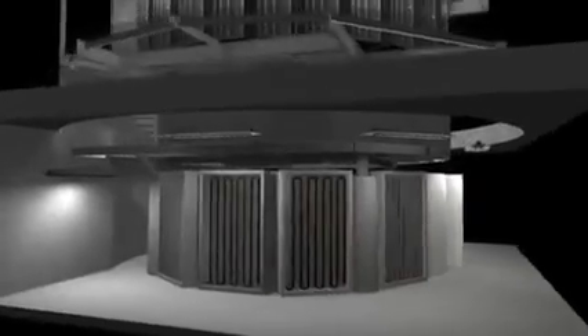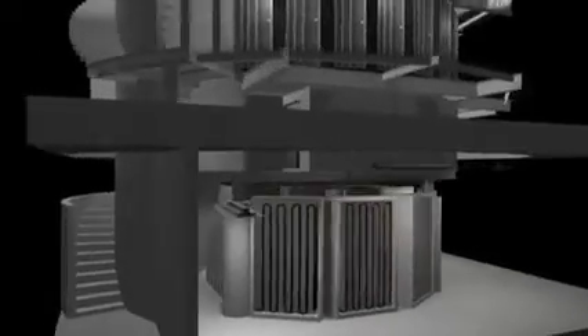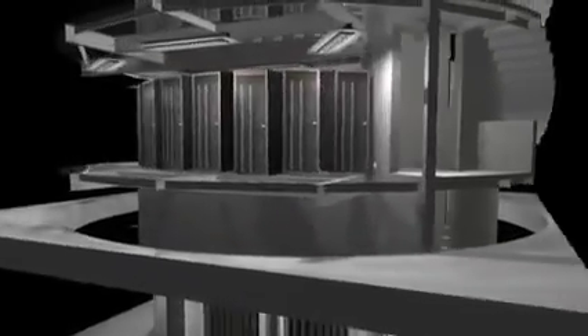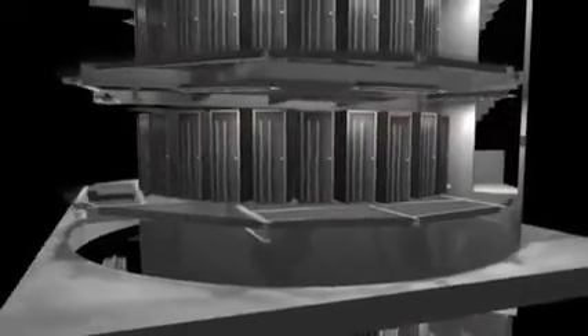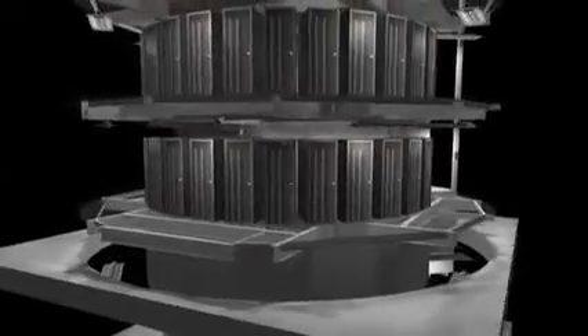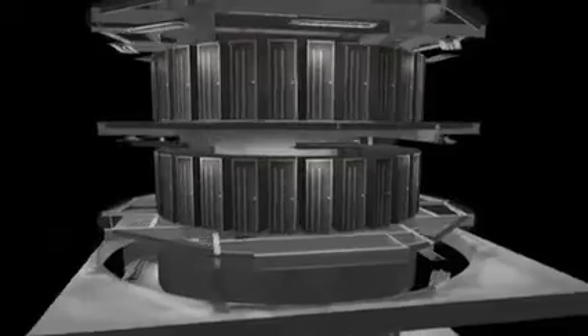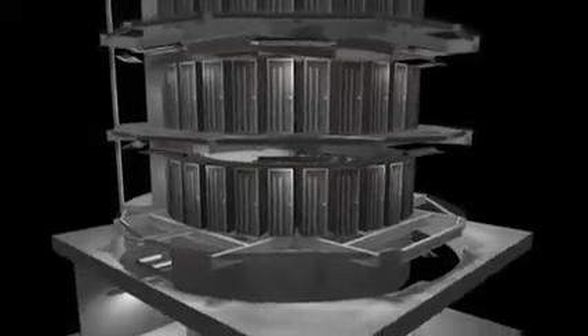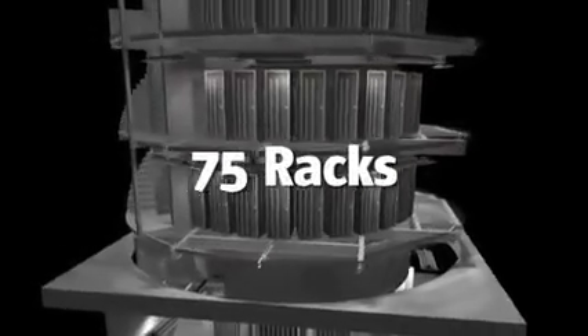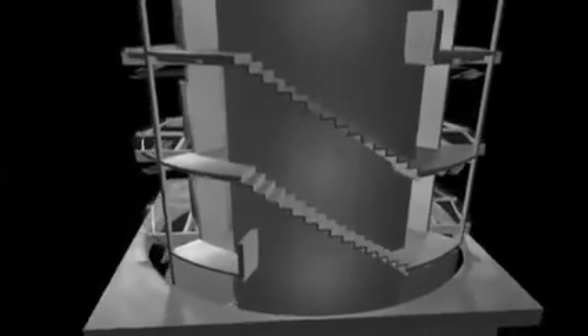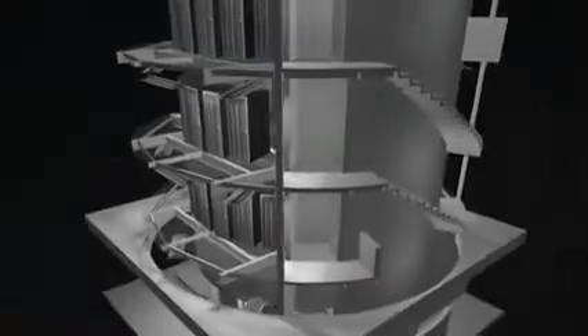The silo is built over 3 floors. You have a sub-basement with all the cooling infrastructure, and then 3 levels of compute racks. By doing this design in a round fashion and centering the switches on the 2nd level right in the center, it was the only way to wire it up to 75 racks within 10 meters length. There's no way you could have done that in a linear fashion, the more typical data center design layout.